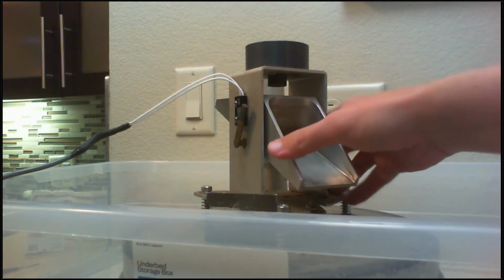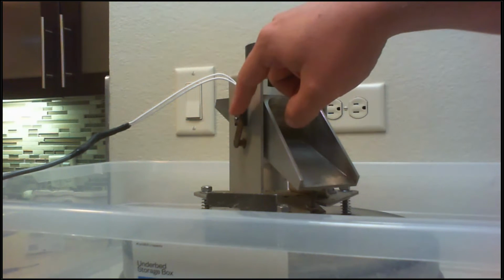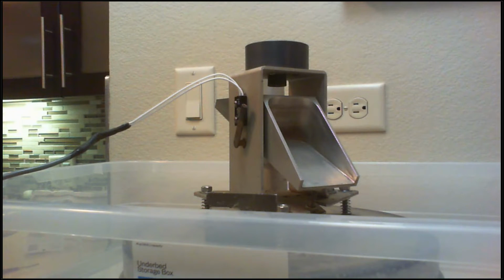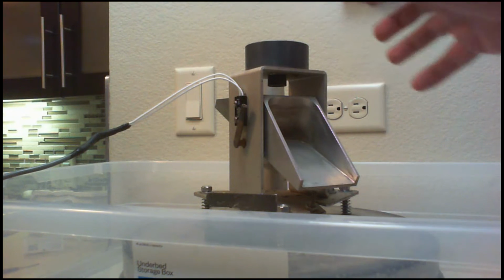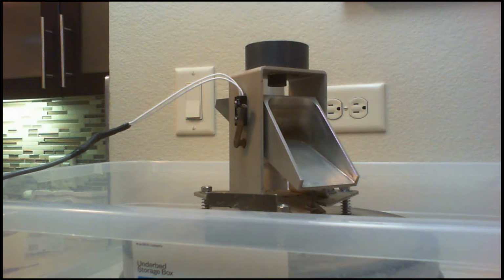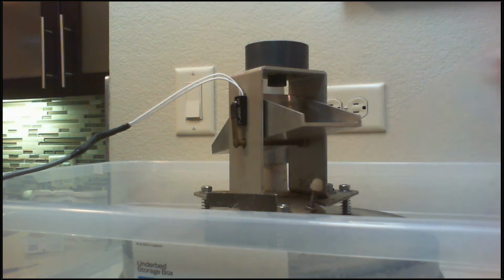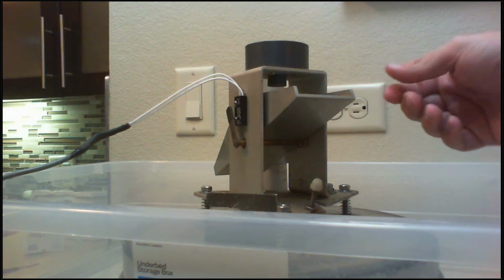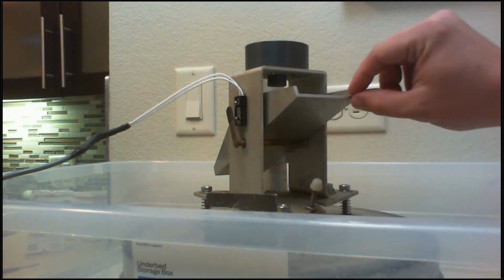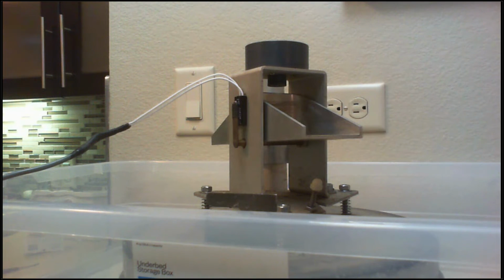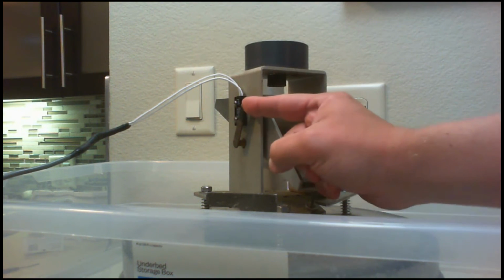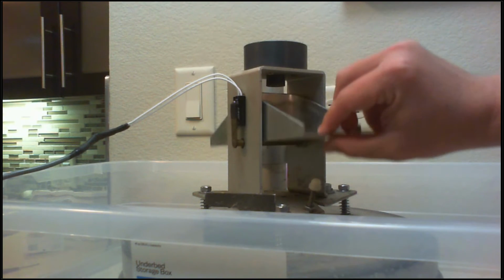While I've got this tipping bucket here, one thing I wanted to show is that I talked about how if this reed switch gets stuck, that doesn't always show up in a static calibration, but it would show up in a dynamic calibration. And that can happen sometimes during installation, or say you were doing some maintenance and you accidentally grab the bucket like that. Well, what happens is when it tries to tip, it gets stuck. This tipping bucket should have clunked, but it didn't, because this switch right here is too close to that little reed switch, and it can actually get stuck halfway in between. And that won't always show up on a static calibration, but it should show up on a dynamic calibration. But just one thing to be aware of is that you want to make sure that that arm is far enough away that it can move smoothly back and forth, but not so far away that it's not picked up by your data logger.